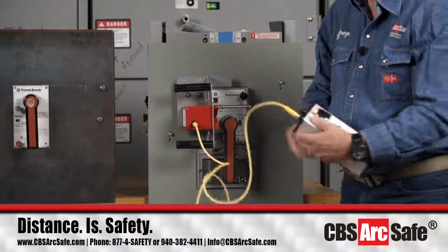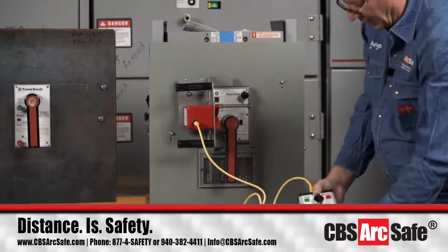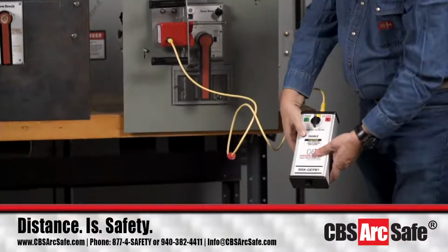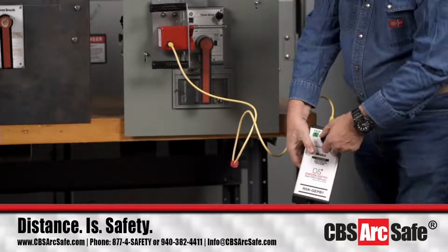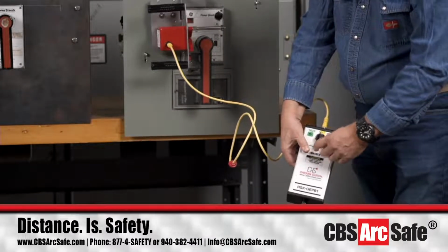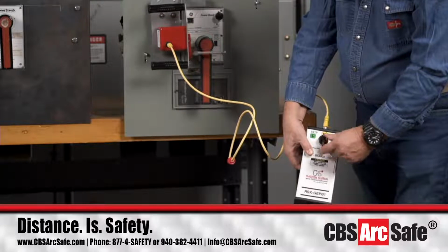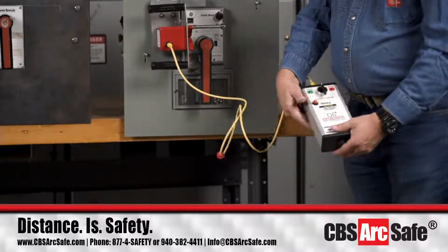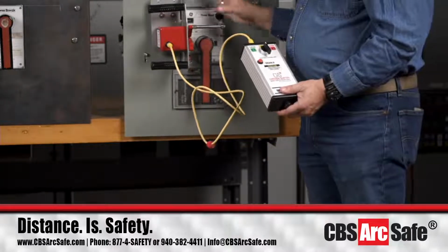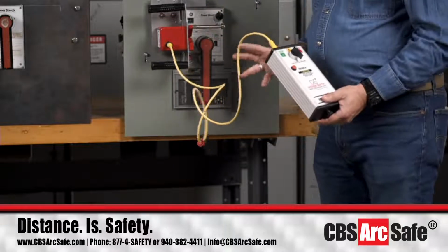Now, for how this is going to work, you'll hold down the enable button, then you'll go to close. And that's its operation. So again, you have to manually charge these, and then you use this for the close and the trip.